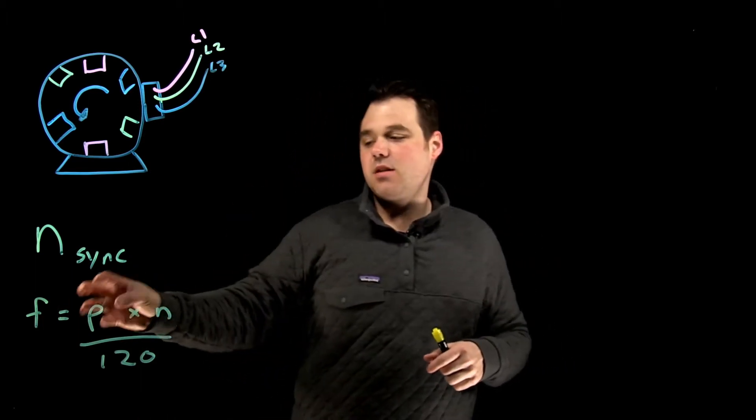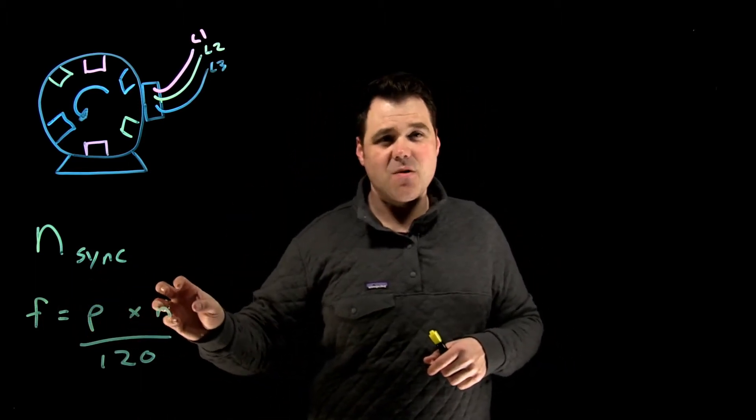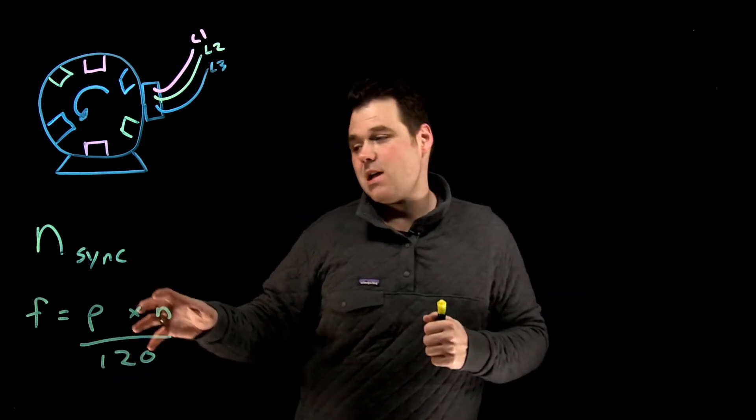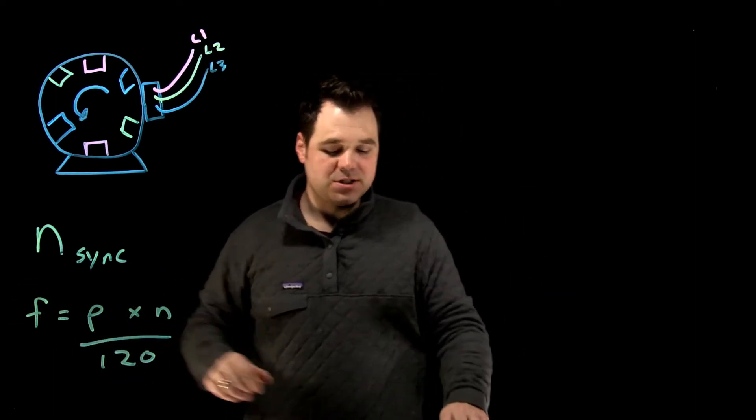...when I'm generating, the number of poles in my generator, the speed I rotate it divided by 120, which is a constant, gives me the actual frequency of the source.